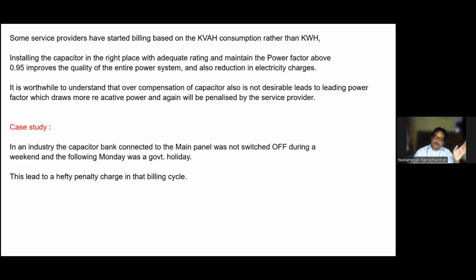So we should go for an APFC panel in the main panel as far as possible. Then automatically, when the SSB is switched off or the motor is switched off, the capacitor will not be in the circuit. So we can easily maintain above 0.9. That is the base. Then while running, it can be maintained at 0.98, 0.97. This is another one of the tips on power factor.